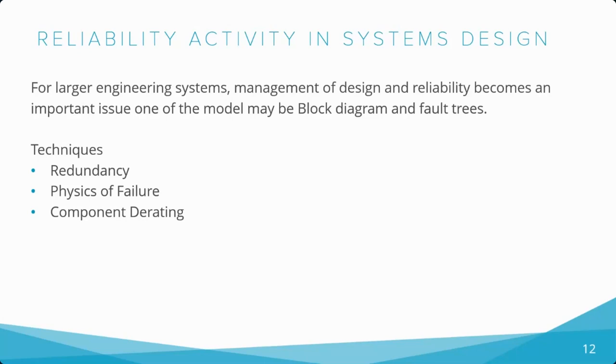As we talked about responsibilities, let's get to know the activities involved in a system design for reliability. Reliability design begins with the development of a model. Reliability and availability models use block diagrams and fault trees to provide a graphical means of evaluating the relationships between different parts of the system. These models may incorporate predictions based on failure rates taken from historical data. Maintainability parameters are also important for these models. The most important fundamental initiation causes and failure mechanisms are to be identified and analyzed with engineering tools.